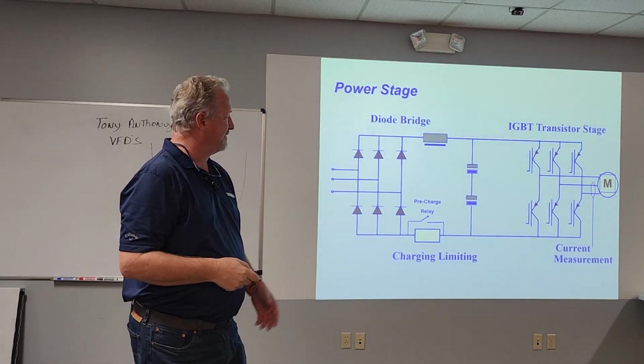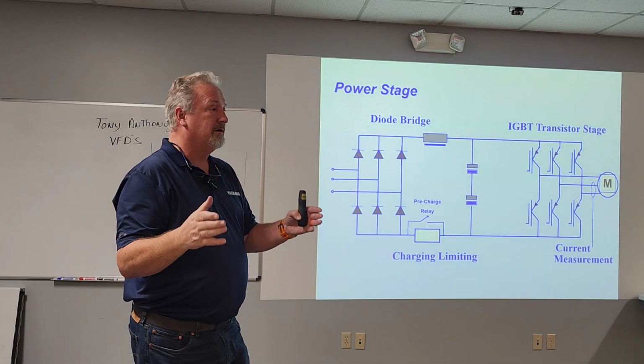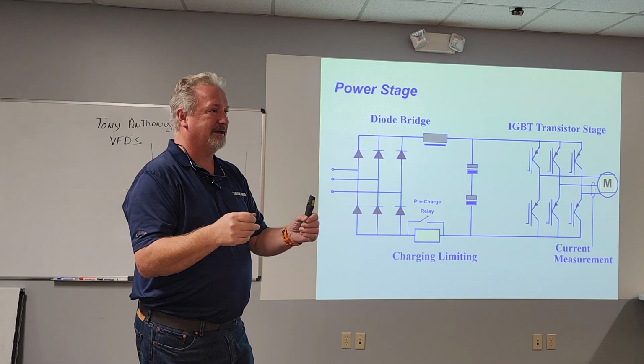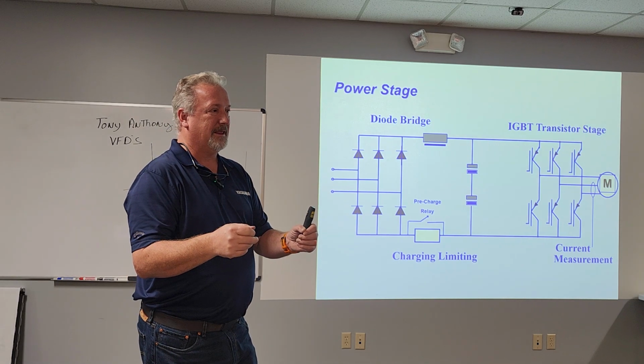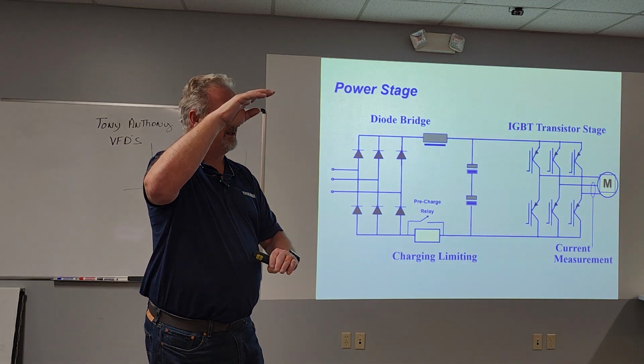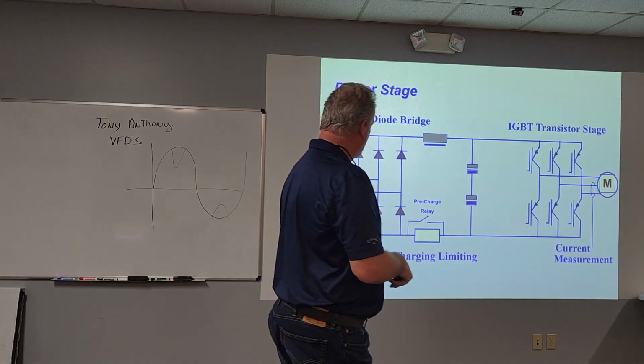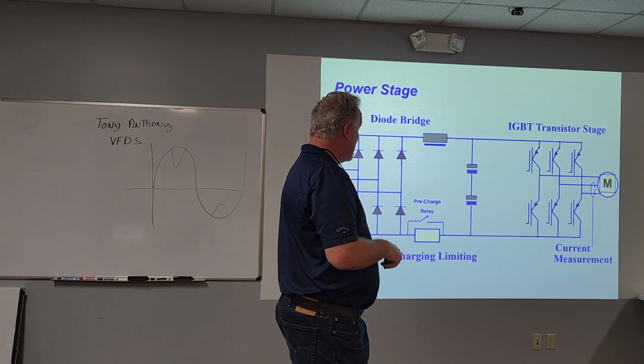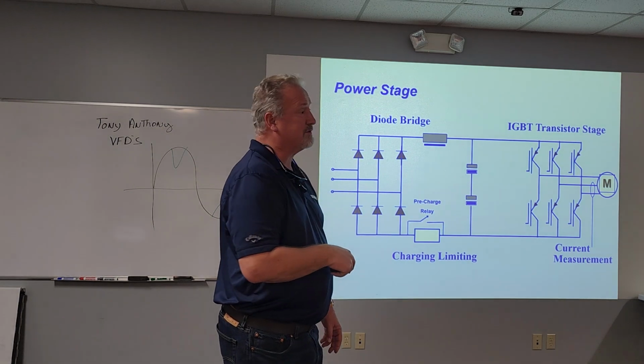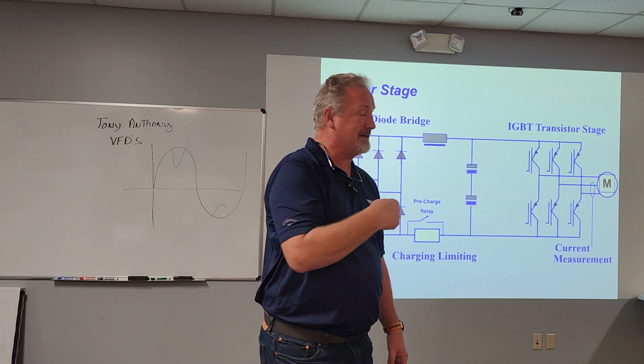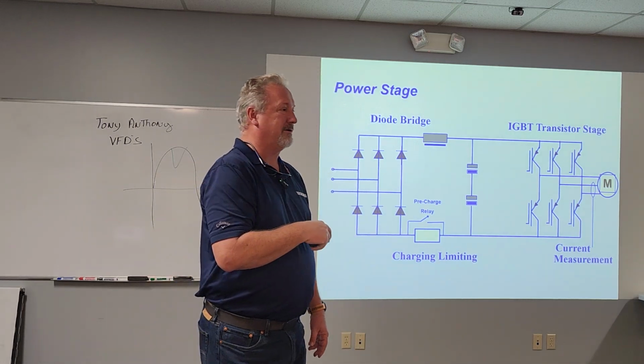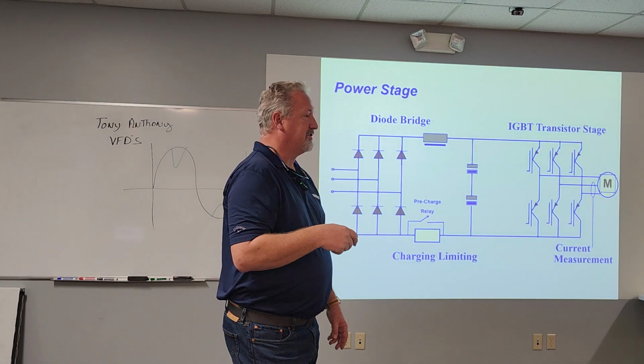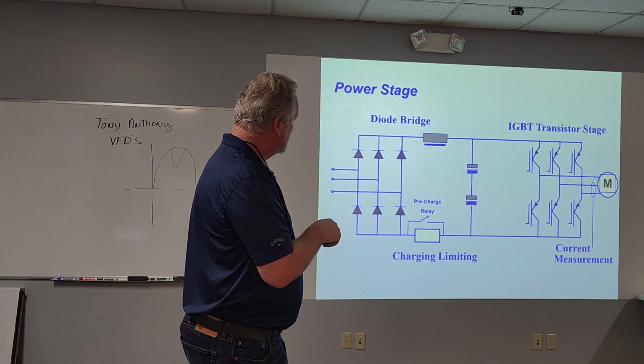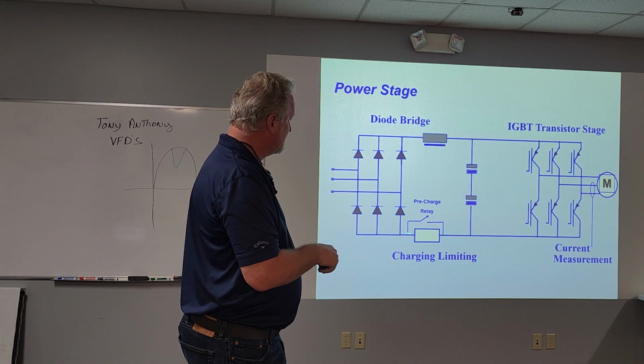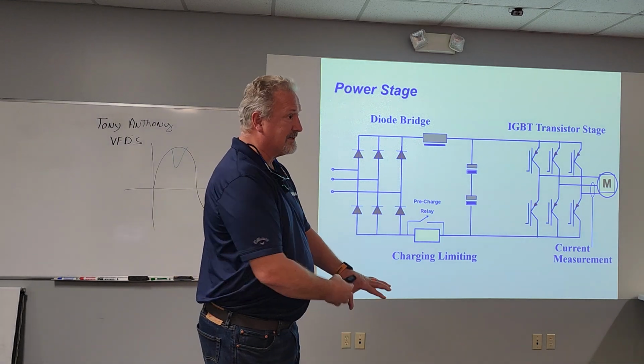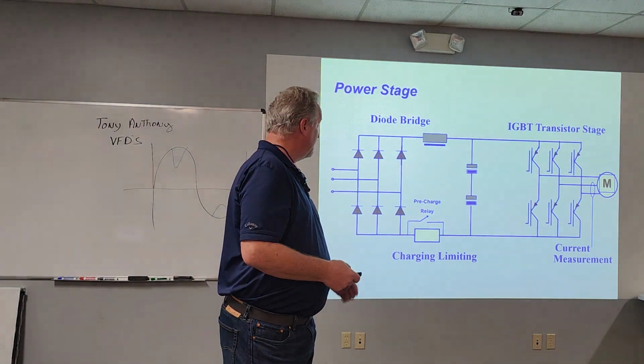Well, when you first apply power to a capacitor, it's an instantaneous short until it starts to charge up. So if we didn't have what we call the pre-charge relay, and this is actually a resistor, a large resistor, in series with the capacitors, every time we applied power to the drive, we'd blow it up. So what we do is we create the DC bus, we charge up these capacitors. This resistor that's here limits the inrush.